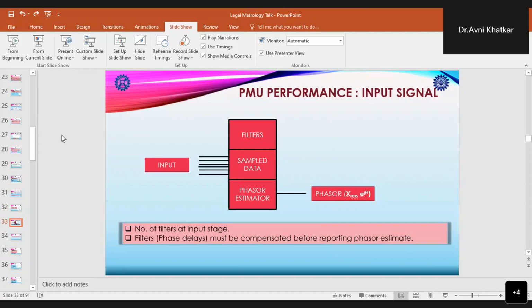Now, after giving the inputs to the PMUs, they are also sampled, and a number of filters are used at the input stages. These filters sometimes cause phase delays. So along with these filters, some compensators are also used, so that any phase delay introduced by the filters must be compensated before reporting any phasor estimate of the PMU. So after giving the inputs, we get output in the form of a phasor, which has an RMS magnitude along with an angle.